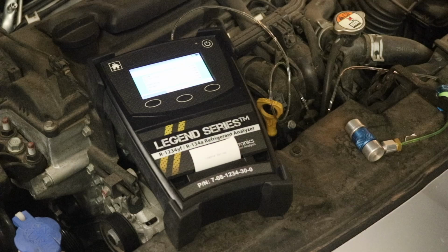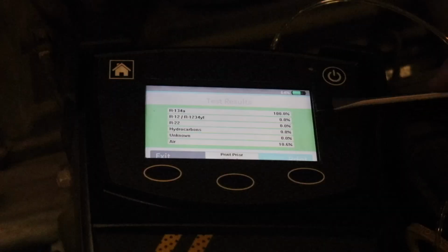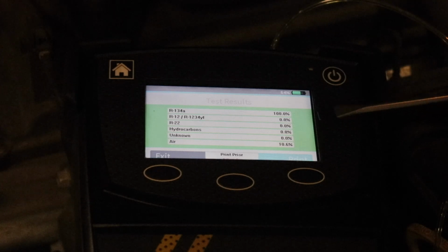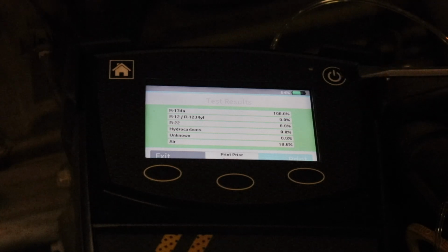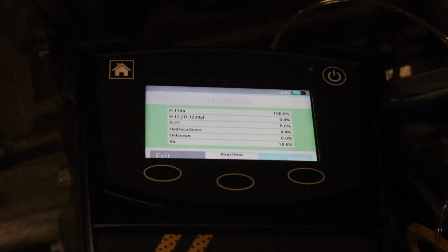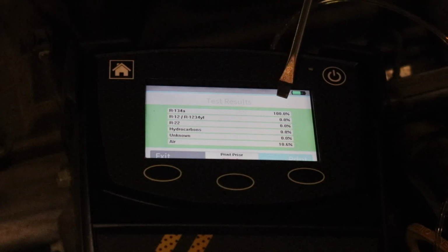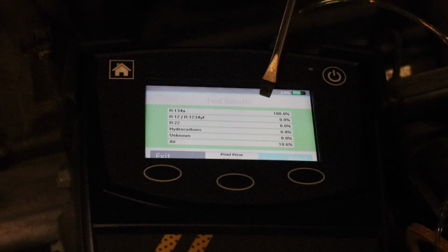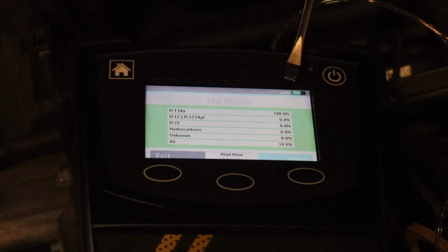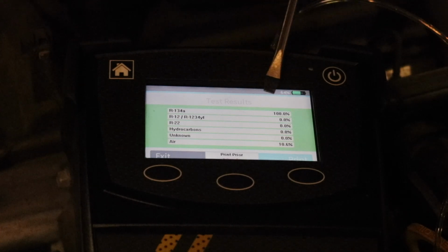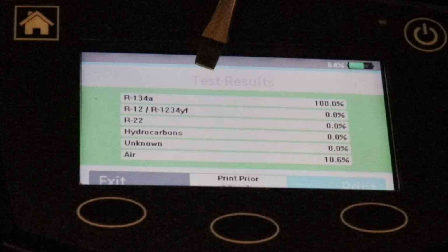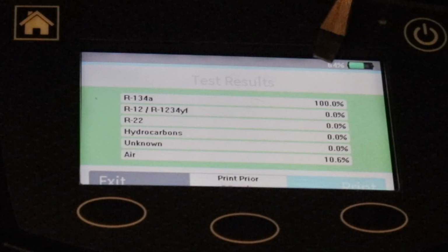Okay, interesting and fairly typical. Let's have a look. Okay, looking at the results as it's been displayed, we can see firstly the background I was just referring to is green, meaning we have reasonably low level of contamination and we have no flammable substances detected. You'll see the top line R134A, which is what we were expecting, has shown as 100%. That means 100% R134A. There is no mixture of refrigerant in this sample.